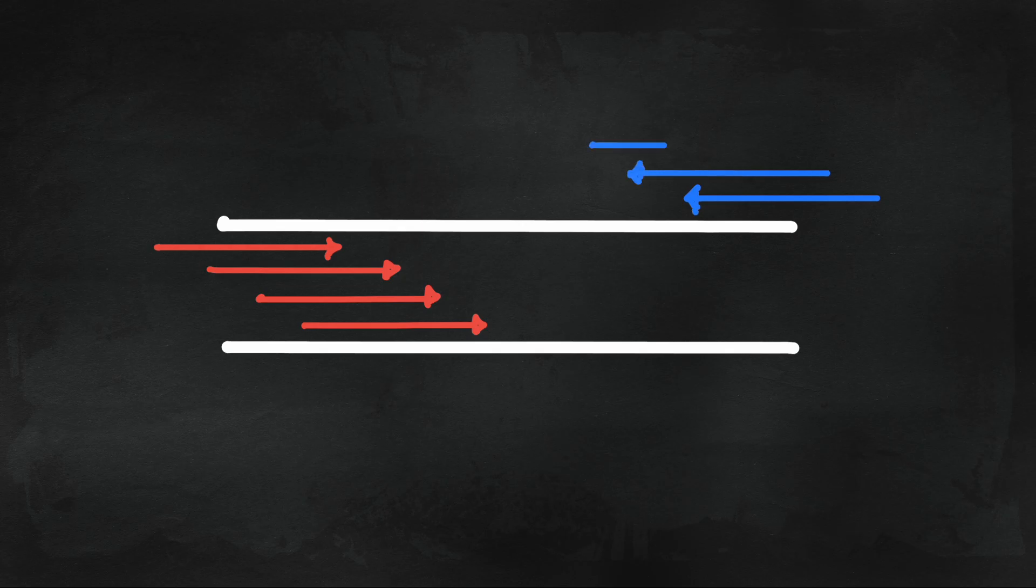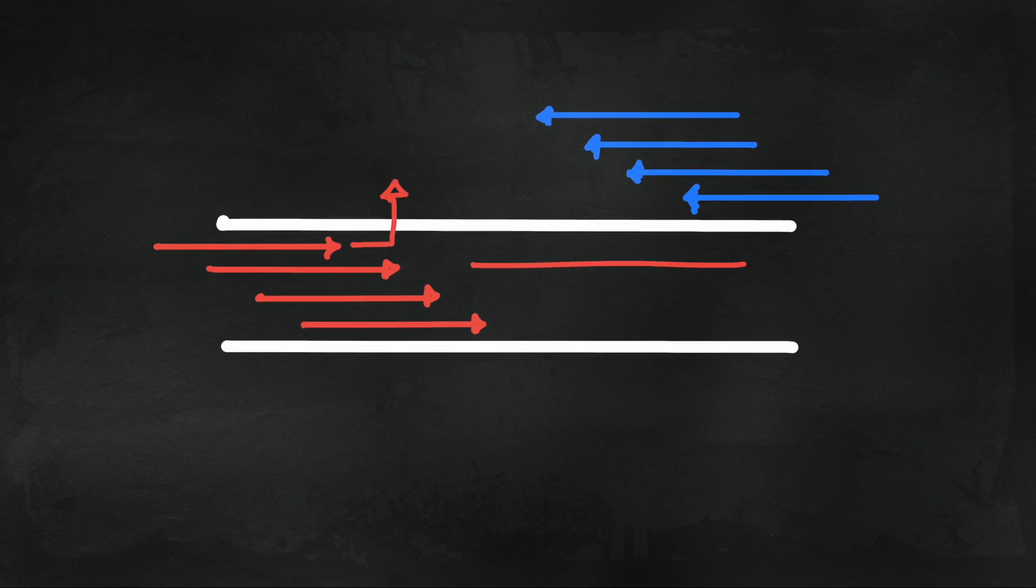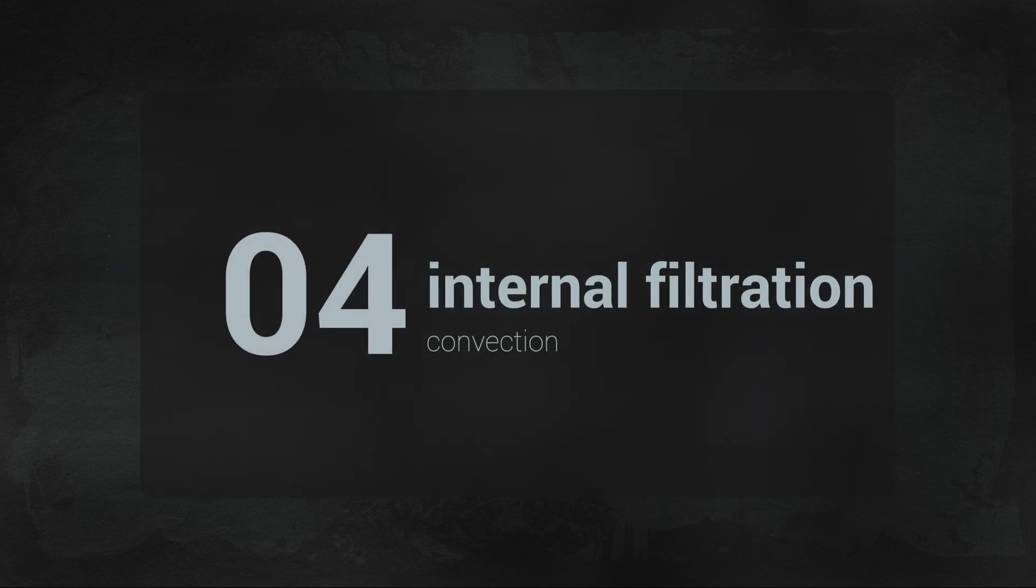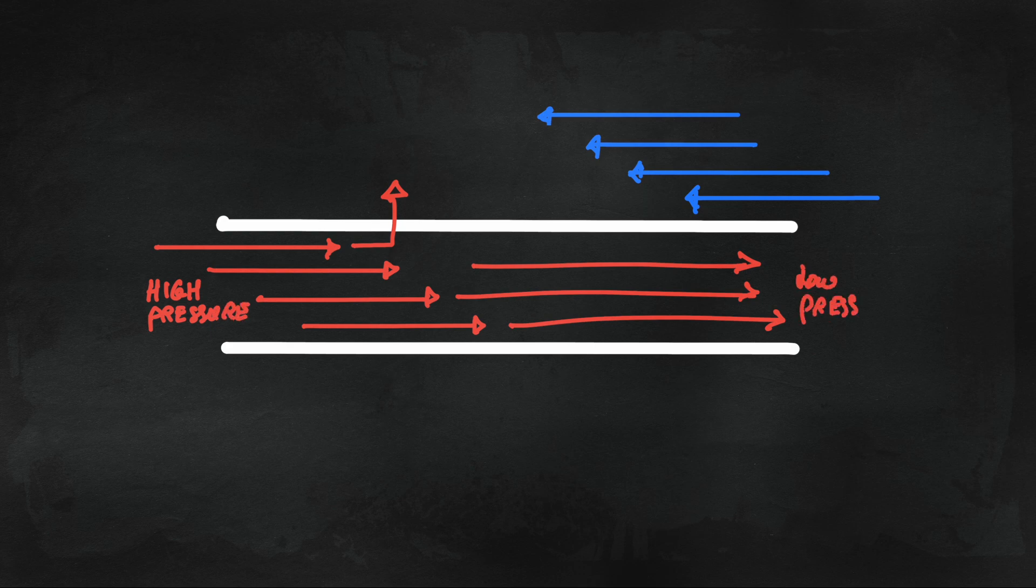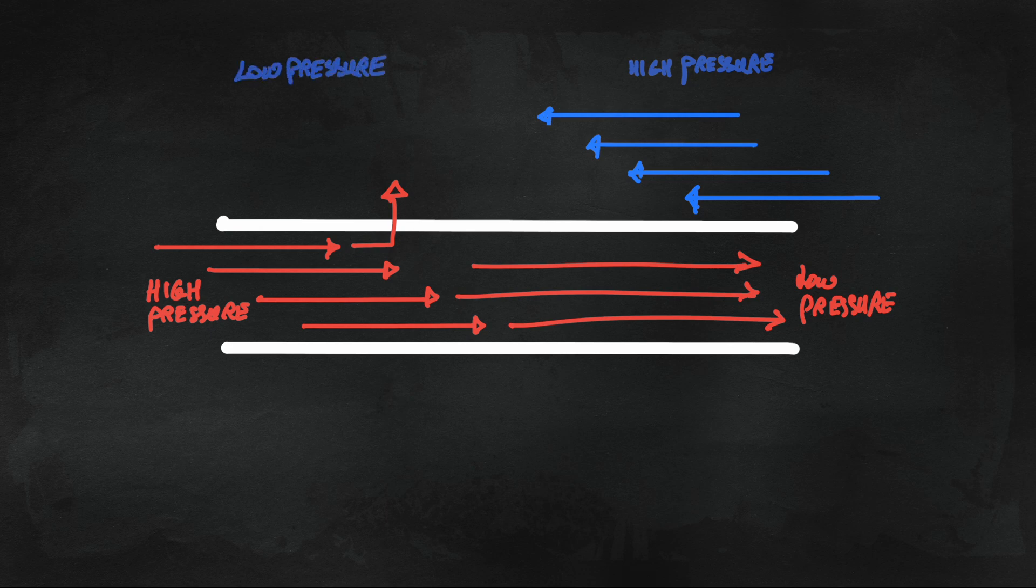Blood flows within the fibers and dialysate around the fibers. Within the filter, due to counter current flow of blood and dialysate, pressure is highest within the fiber at the blood entry side. In a membrane with a high UF coefficient, you will have significant filtration at the blood entry side above and beyond the UF prescribed.